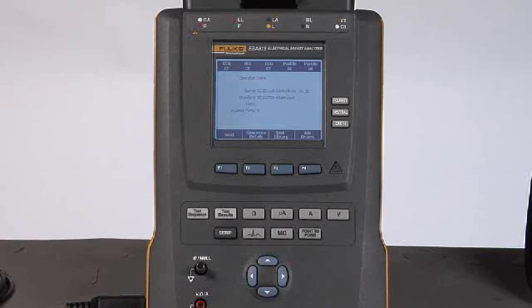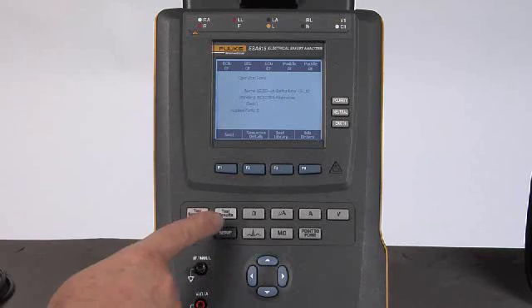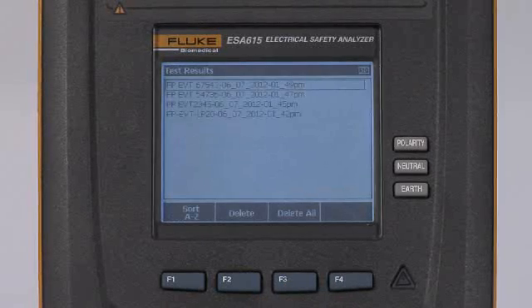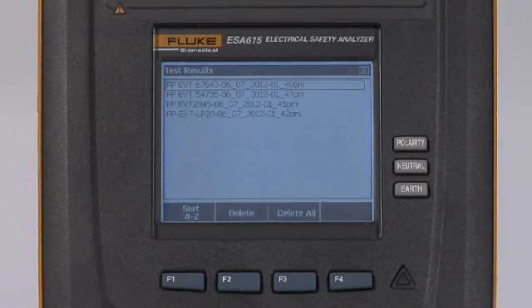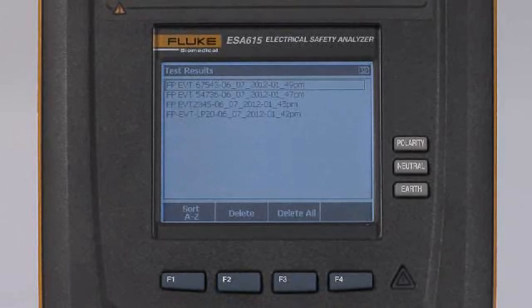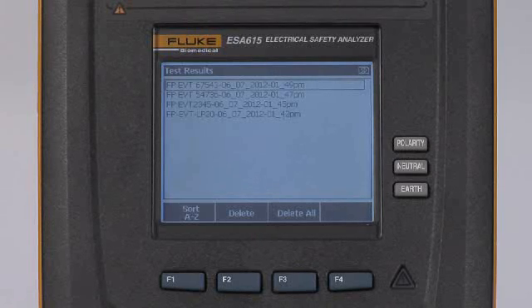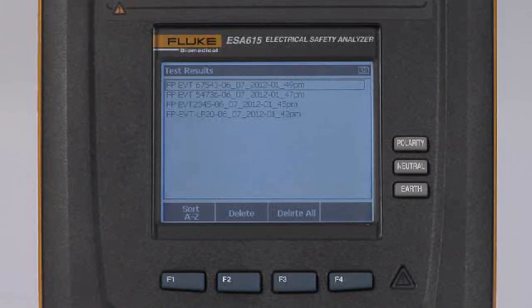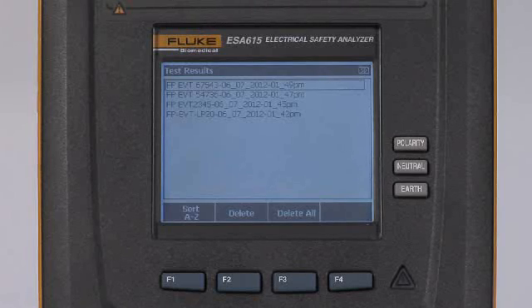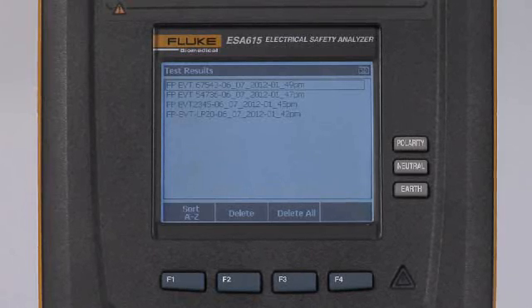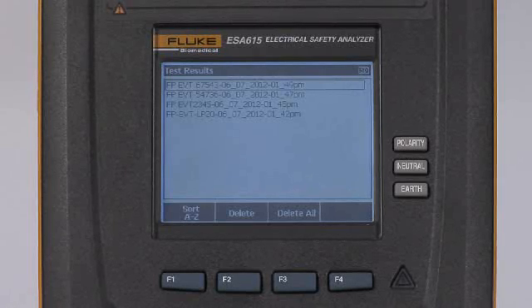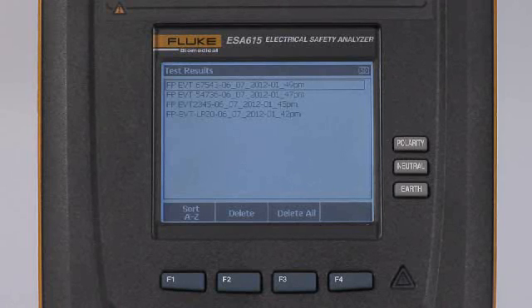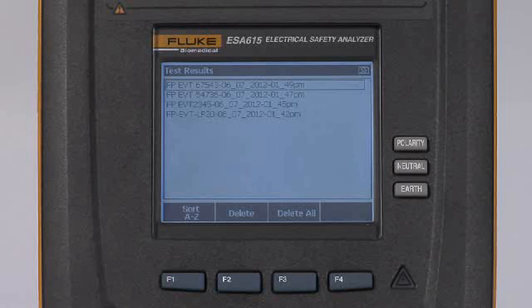Well, what if I want to review the test results from tests that I have run during the day today or during this last week or however long? I will pick the test results button, and it will list all of the test results that have been stored in onboard memory on the ESA615. The F1 button allows me to sort them in alphabetical order. The F2 button allows me to delete the test results that I have identified, or F3 allows me to delete all—and that assumes that I have archived those test results to some other device like my computer, or I have printed out my test results.